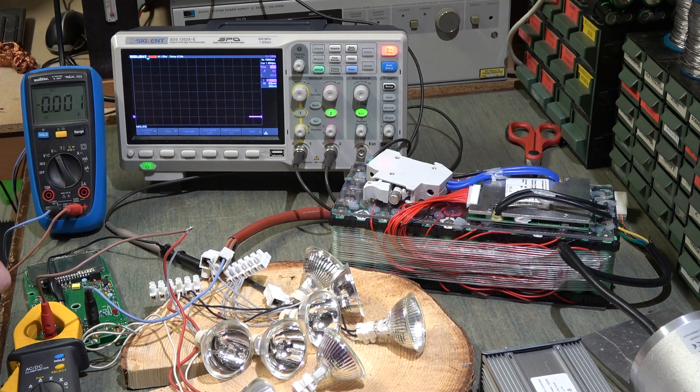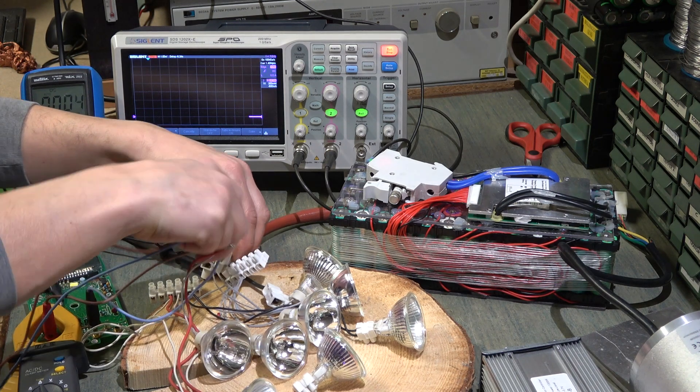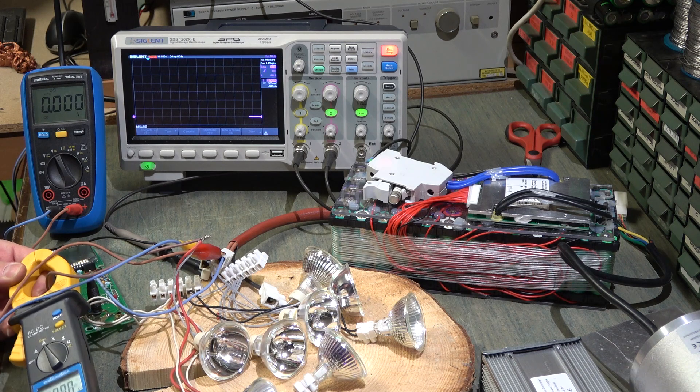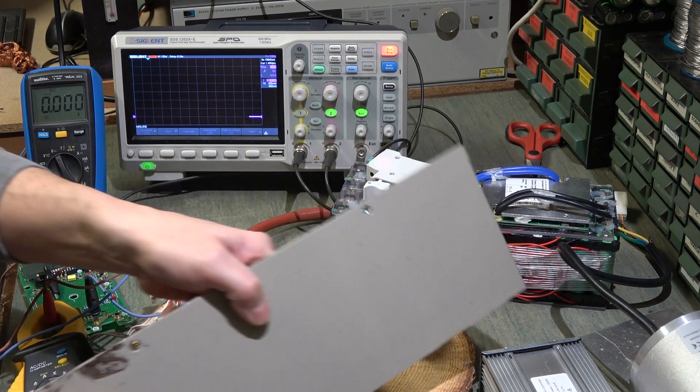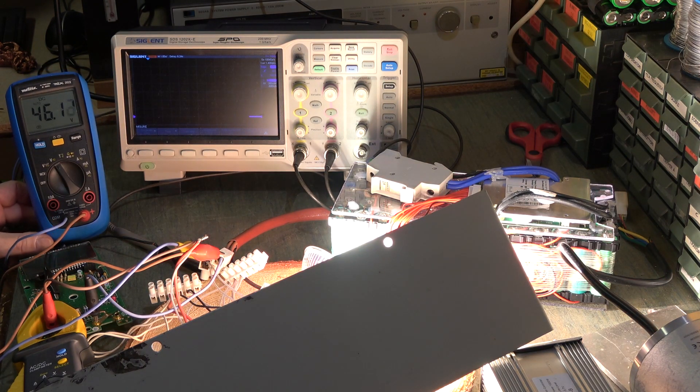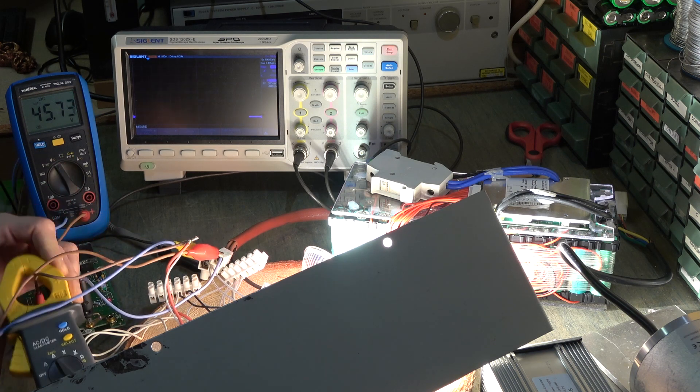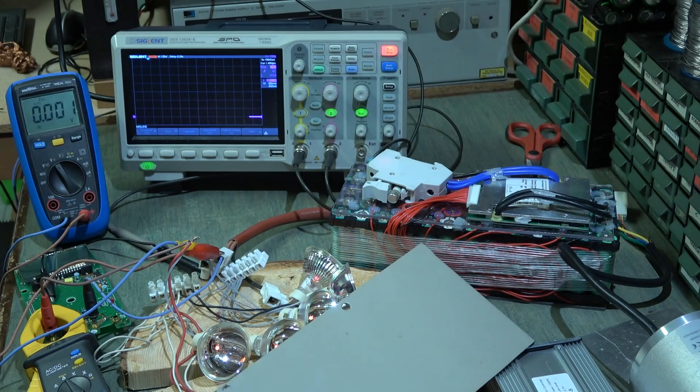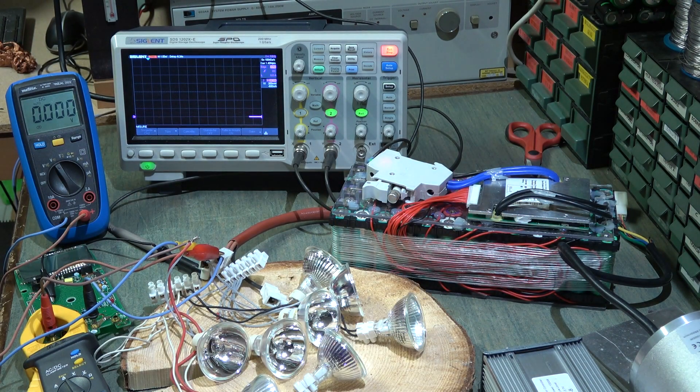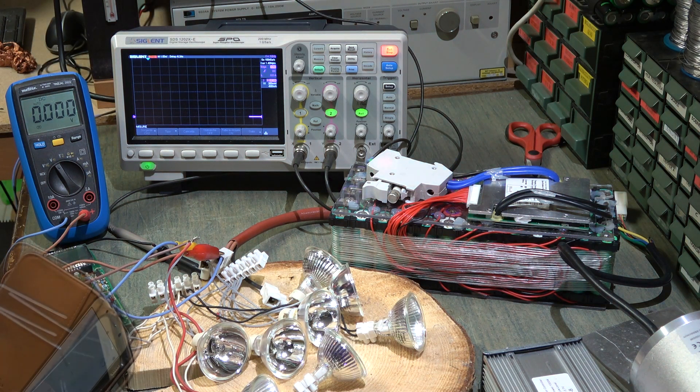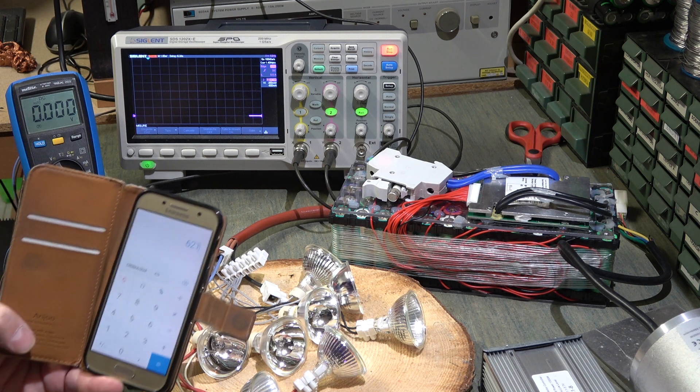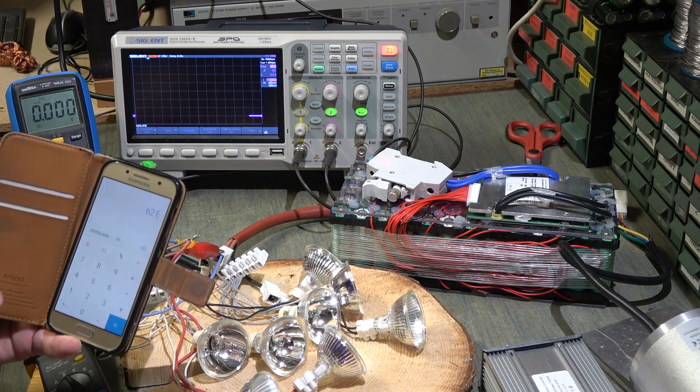Ora misuriamo anche la tensione. Mettiamo ancora il nostro coperchio e vediamo 46 volt. 46 volt con la pinza amperometrica che mi segna 13 ampere e mezzo. Evidentemente 13 ampere e mezzo per 46 volt, facciamo il calcolo: 13,5 per 46 volt uguale 621 watt. Abbiamo attaccato un carico di 621 watt.